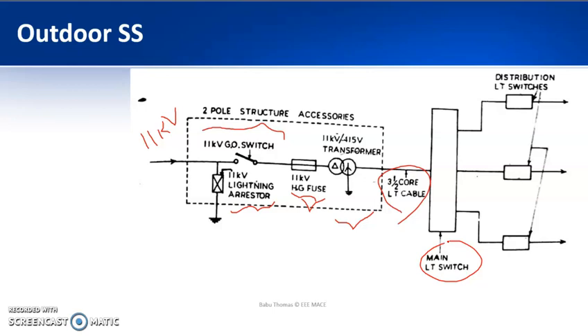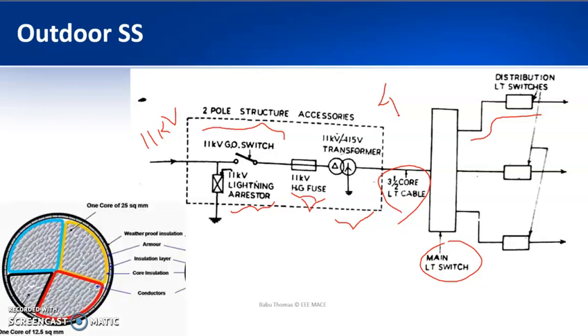And then it will go to the distribution low tension switches, depending upon the capacity of the system. Here you can see that this transformer is a delta star system. So at the secondary side you will have 4 cables, that is R, Y, B and neutral, and that is why it is written as a 3.5 core LT cable. And what is a 3.5 core? You can see it over here. So this is a 3.5 core. Totally 4 cores are there, 1, 2, 3 and 4.